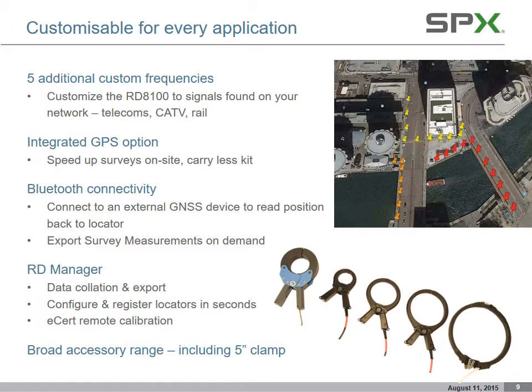And there is a new ring clamp. They offer a 5-inch ring clamp with the RD8000s, 8100s, and 7000 transmitters. And so this 5-inch ring clamp is much needed because the 4-inch ring clamp will not fit around a 4-inch pipe, but now the 5-inch will. So they have that in between the 8.5-inch, which is their largest, and the 4-inch ring clamp. And they, of course, still offer the 2-inch ring clamp and the current direction ring clamp.